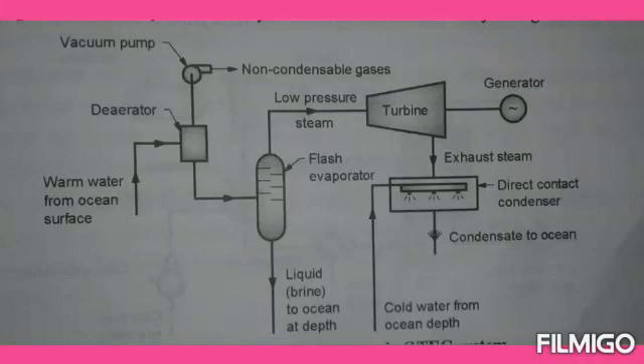In the open cycle system, warm water from the ocean surface is taken into a deaerator where air is removed using a vacuum pump, and non-condensable gases are also removed from the warm water. That warm water is then supplied to a flash evaporator where evaporation of the warm water takes place. The remaining liquid brine is released at depth to the ocean, and the steam generated in the flash evaporator is passed to the turbine.